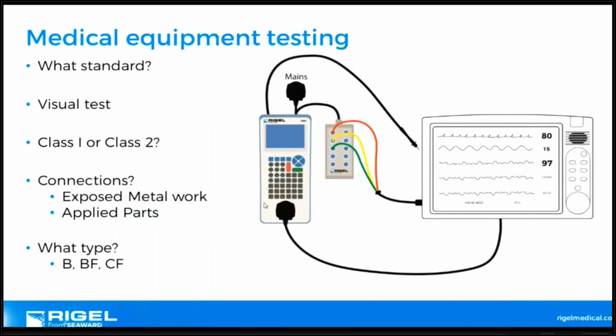So if I'm in a healthcare organization and I want to do electrical safety, there are a number of questions that I need to ask myself. What standard am I testing to? Is it 60601? Is it 62353? Is it NFPA 99? Globally, these are 3 different standards typically used for testing medical equipment. This could be a decision that is in-house. This could be driven from some regulatory agency or authority, or it could be something that you follow within, like I said earlier, an alternative equipment maintenance schedule where you would just follow the guidance of the electrical medical equipment manufacturer.